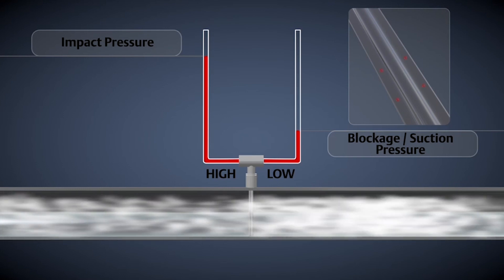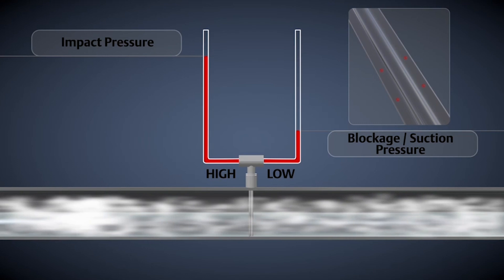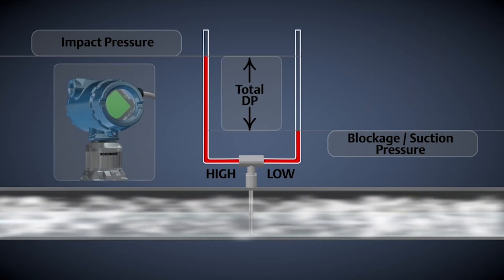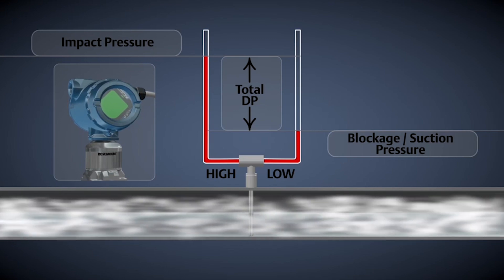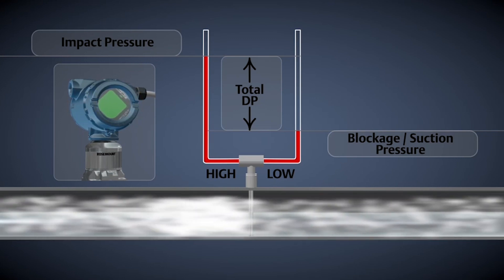The low pressure is sensed by the holes on the back side of the sensor. The difference between the high pressure reading on the front side of the bar and the low pressure on the back is the differential pressure sensed by the DP transmitter.